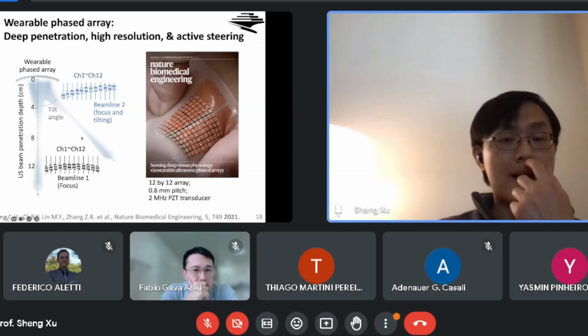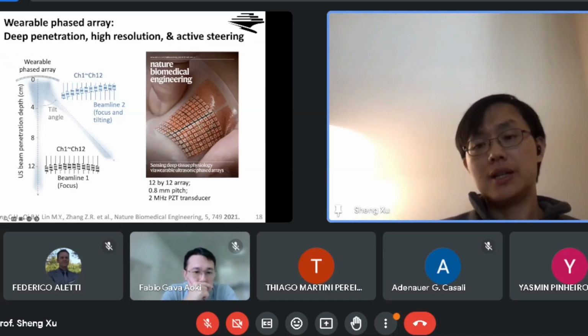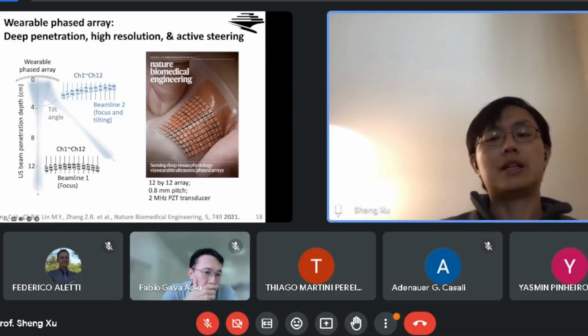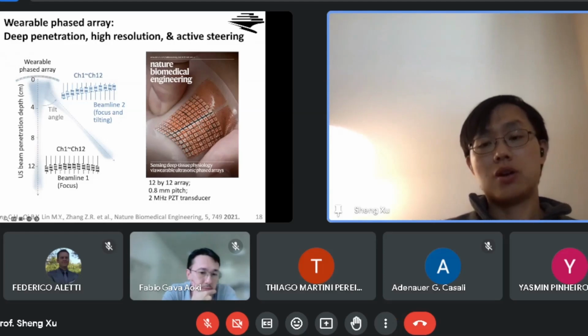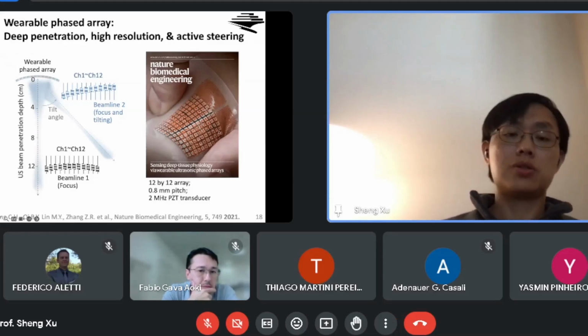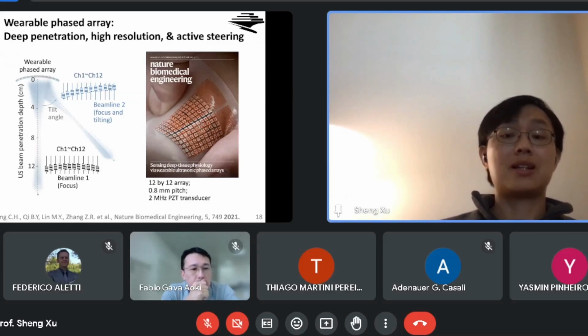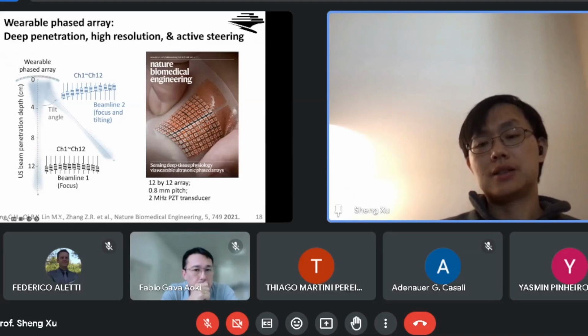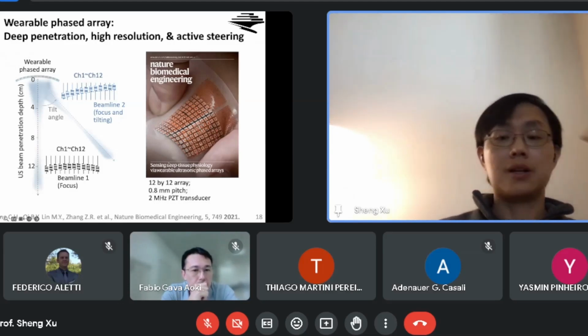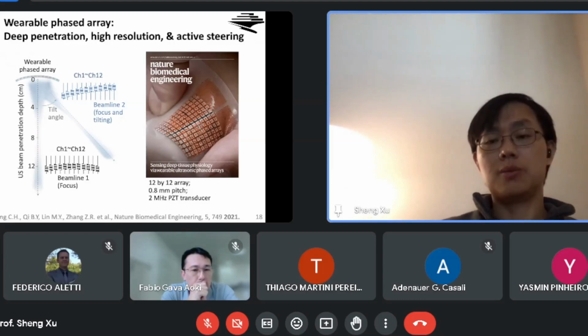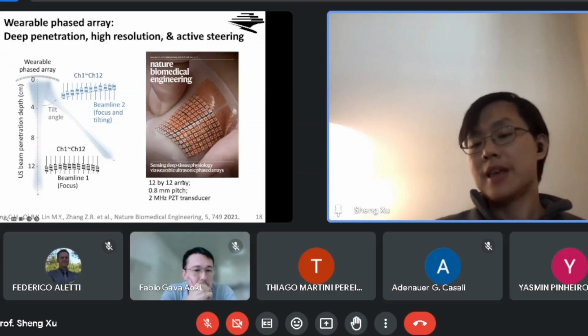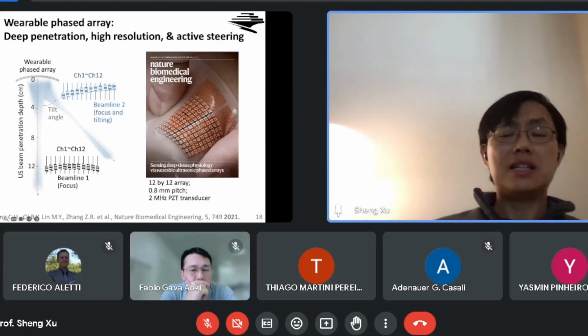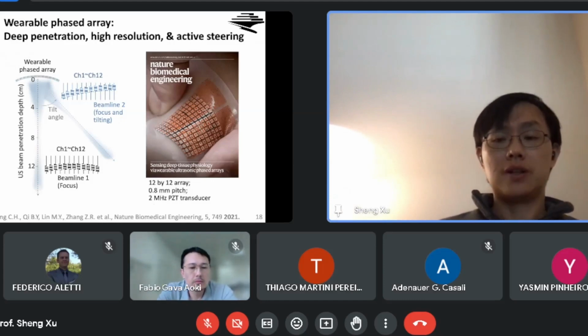So this is the phased array control mechanism, and this is the phased array. As you can see here, this phased array is much larger and denser than the previous ultrasound device I showed you. It's a 12 by 12 array with 144 elements, because we want to transmit more ultrasound energy into the human body so that it can penetrate deeper. The second thing is that the distance between the elements is smaller, because we want to minimize the so-called side lobe, grating lobe, to minimize those artifacts. The third thing is that we have used a low frequency of 2 megahertz, in comparison with the 7.5 megahertz in the previous case. These two methods can enhance the insensitivity of this device to morphology deformation. What does that mean? I will show you in the next few slides.